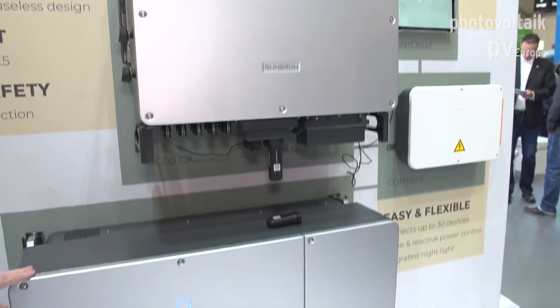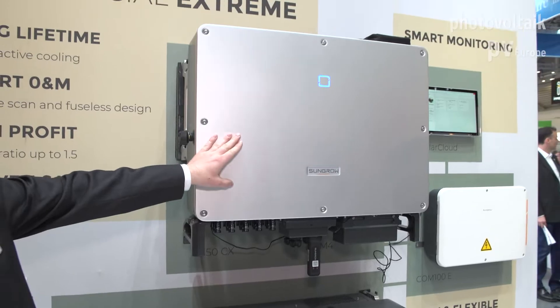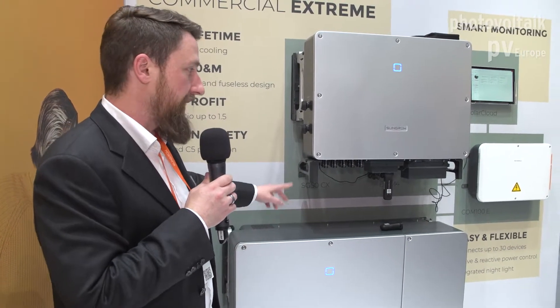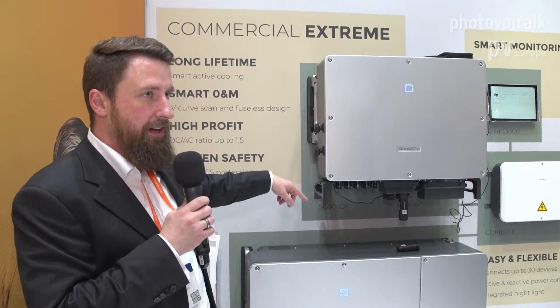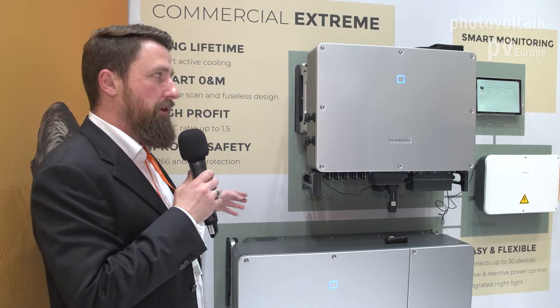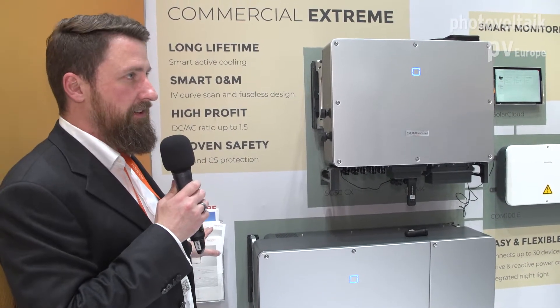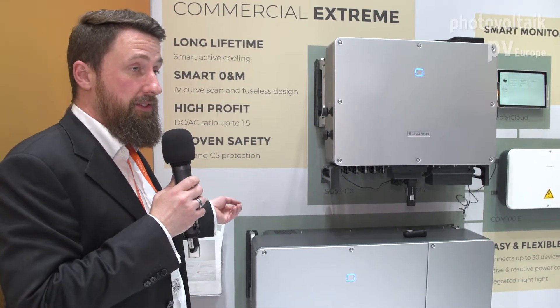These are available with three, four, and five trackers depending on the power class. The big one has nine MPPTs. Each tracker has two inputs and each connector can handle up to 30 amps, so you can connect Y adapters and bifacial modules and get the most out of your PV installation. As a rule of thumb we recommend not exceeding a DC/AC ratio of 1.5, but depending on your setup you can go well above 1.5.